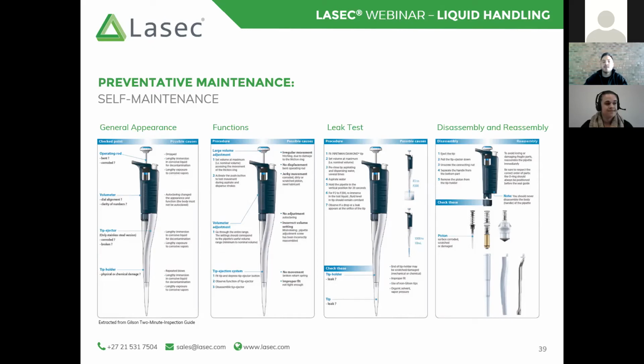After you've done the general appearance check, you have noticed nothing of any significance on the exterior of the pipette, it is now important to do a functional test. And the reason we do a functional test with an air displacement pipette is that the piston is hidden inside of the pipette. You aren't actually able to see the mechanism inside. So you want to make sure that the piston is still in good working order, that the seals and O-rings ensuring that the piston is seated firmly in that tip holder haven't worn out, and also that the tip that you are using is actually appropriate for that pipette.